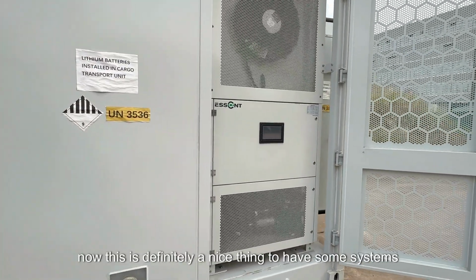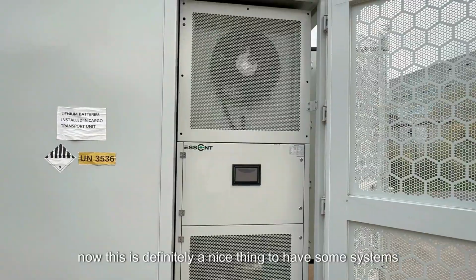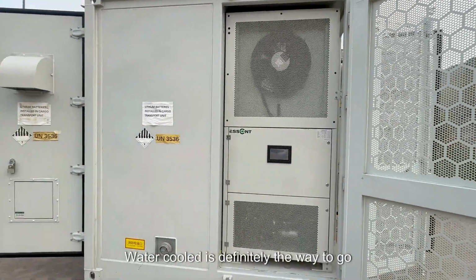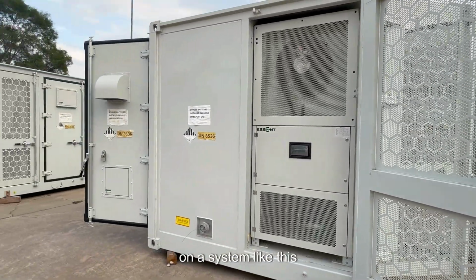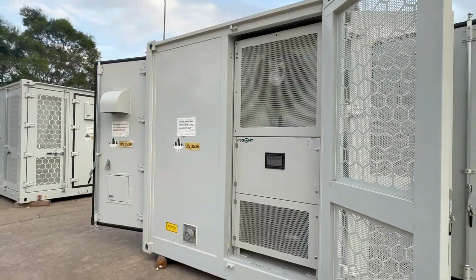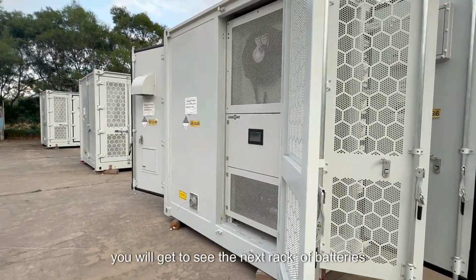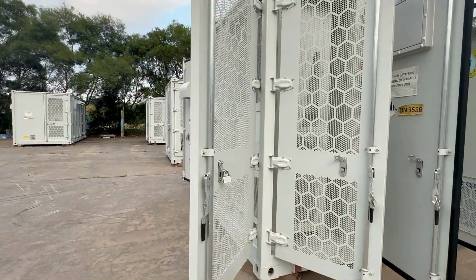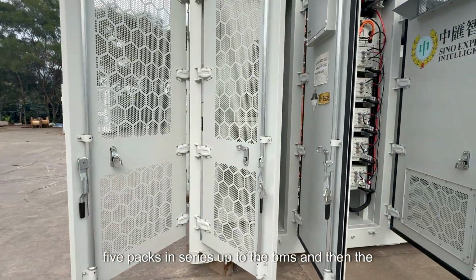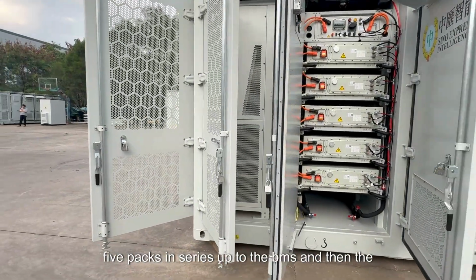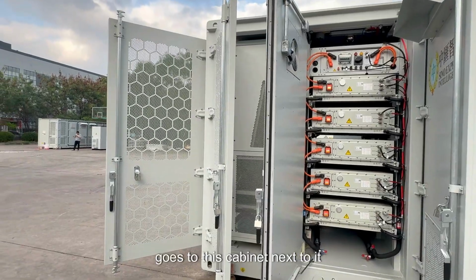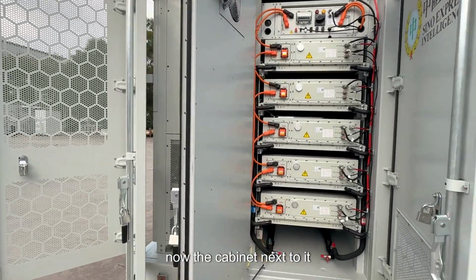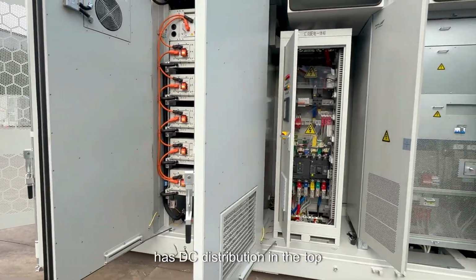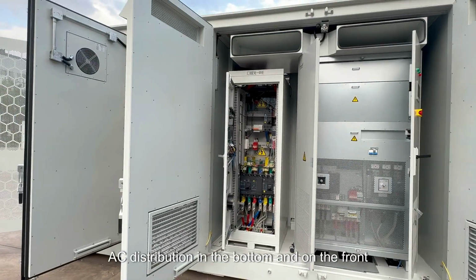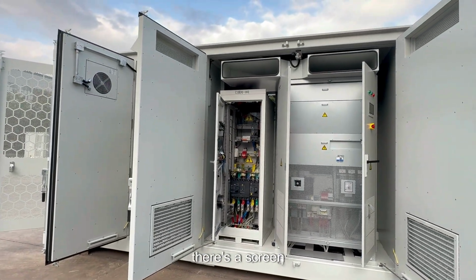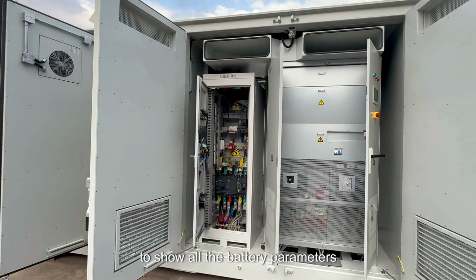Now, this is definitely a nice thing to have. Some systems are passively cooled or air cooled. Water cooled is definitely the way to go on a system like this. As we come around the corner a bit further, you'll get to see the next rack of batteries. So same again, 5 packs in series up to the BMS, and then the BMS goes to this cabinet next to it. Now, the cabinet next to it has DC distribution in the top, AC distribution in the bottom, and on the front there's a screen to show all the battery parameters.